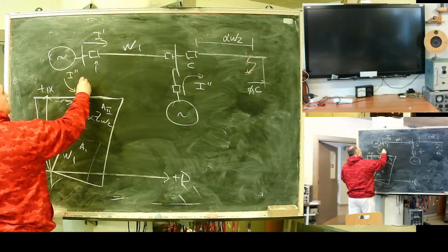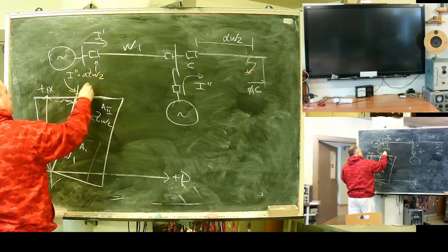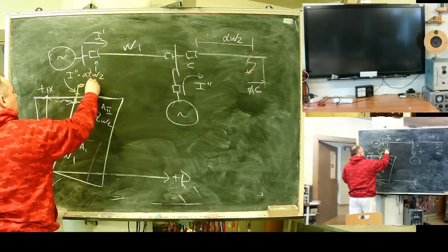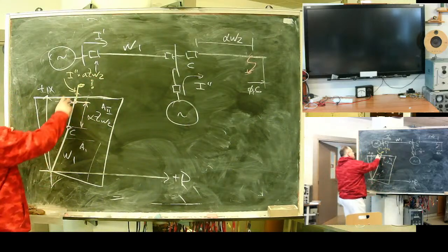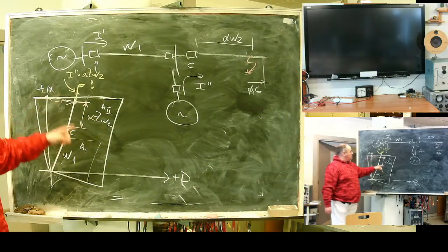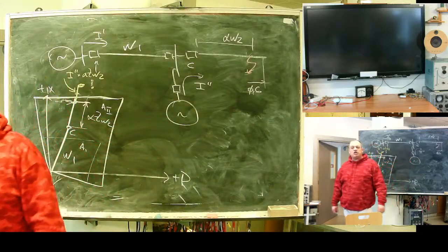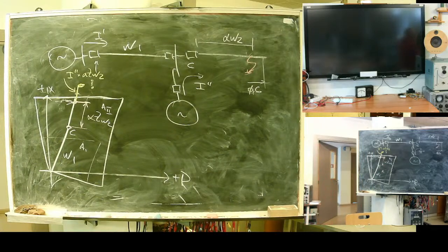This part is I multiplied by alpha, and here is the resistance my protection will see because of the second current. The flow of second current from the second source shifts the observable point forward. This effect is called zone shortening.